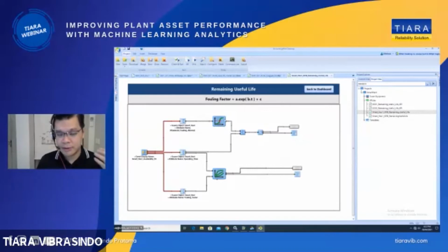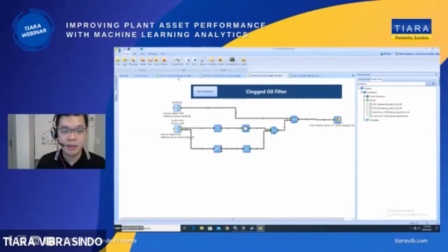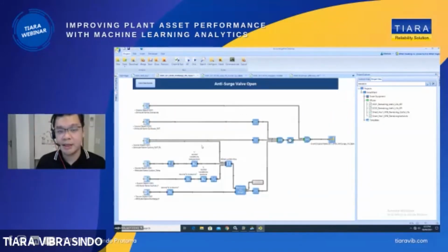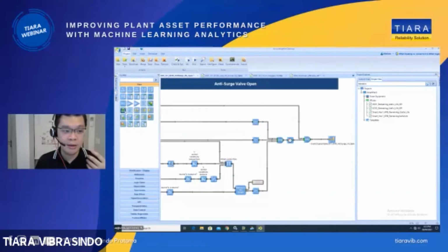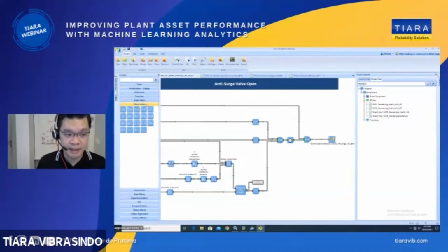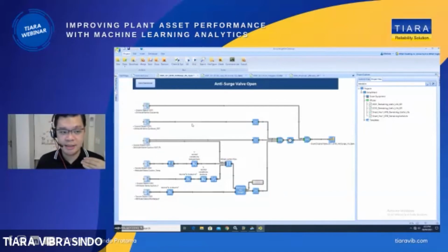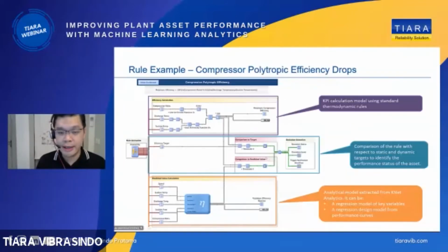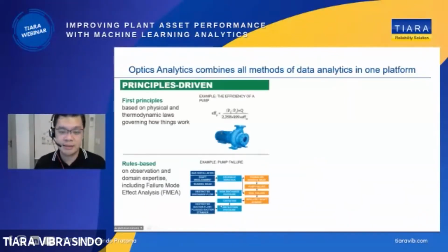So there are places where you need to use models. There are places where you can simply use calculations. And there are places where you can use all the different statistics, SPC algorithms, or different methods to reason out whether there is an abnormal condition or not. So a good industrial software for detecting equipment abnormal conditions is one that combines principle calculation and machine learning, not just only doing machine learning.